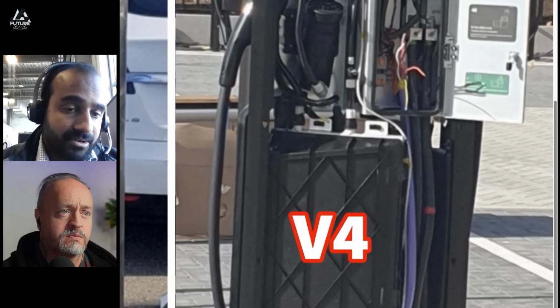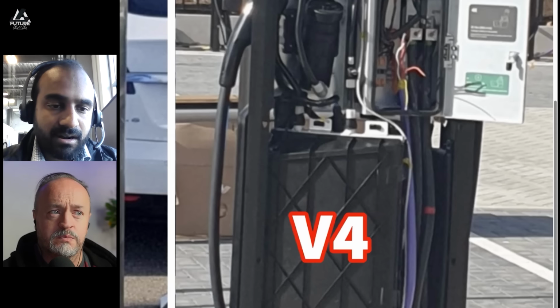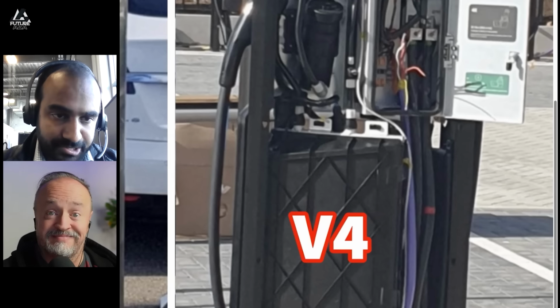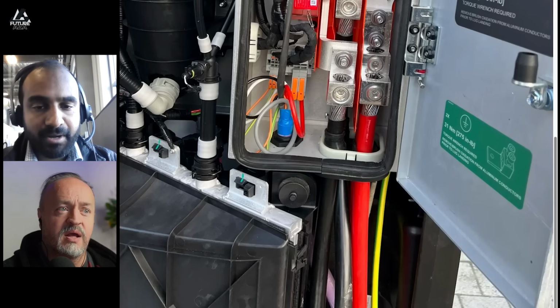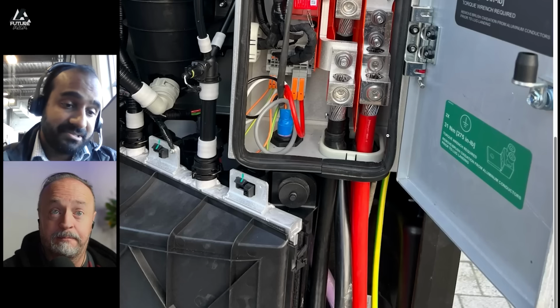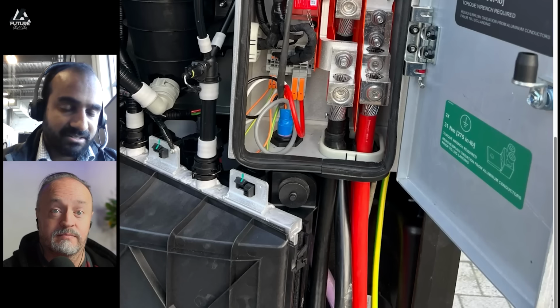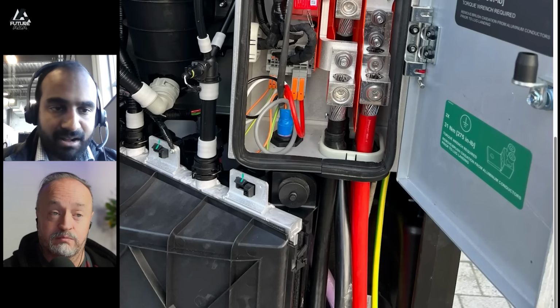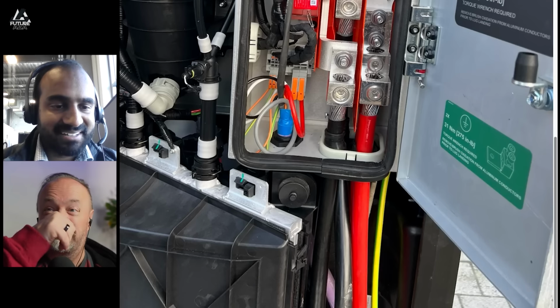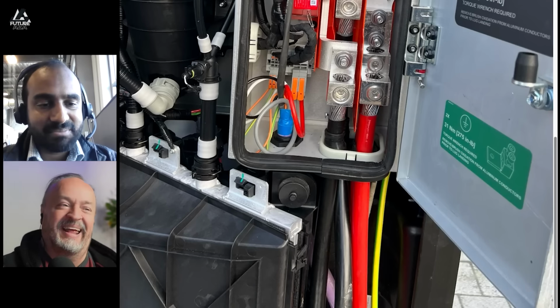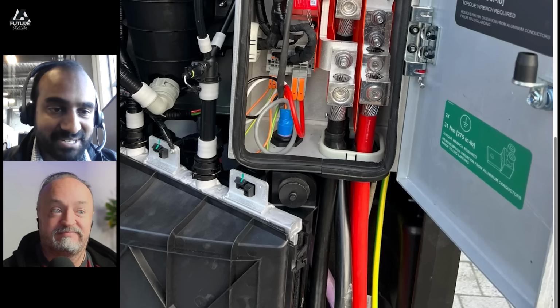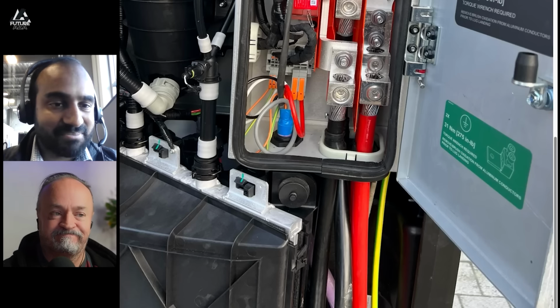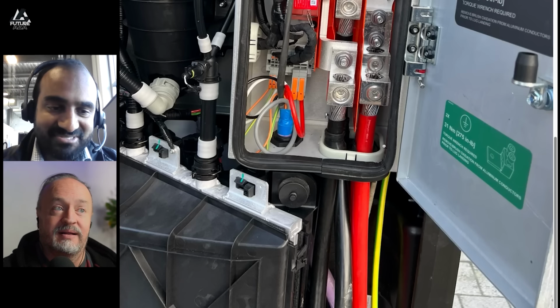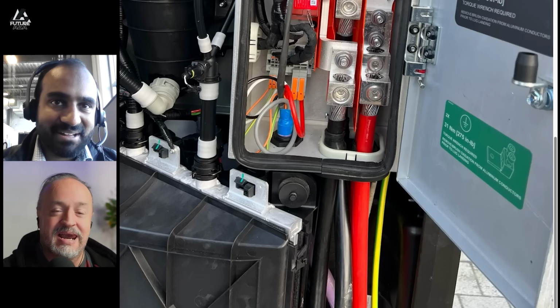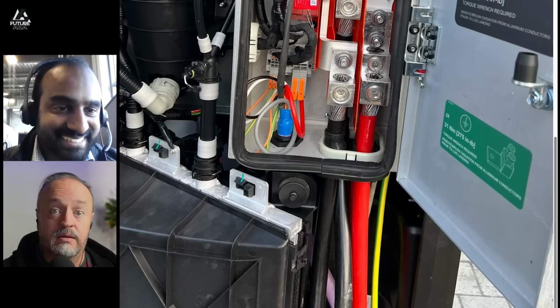But certainly the overall dispenser has a far higher cooling requirement than the original V3 dispenser. The V3s used to rely on letting the cable get hot and then backing off the current as soon as it got too hot. People started defeating the system by wrapping towels over their connectors, and Tesla actually had to come out and tell people to stop doing that.